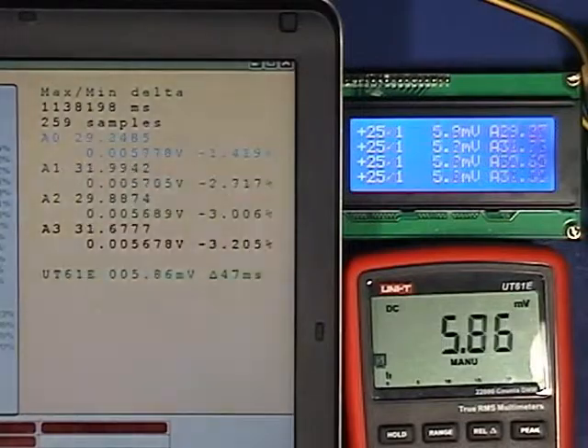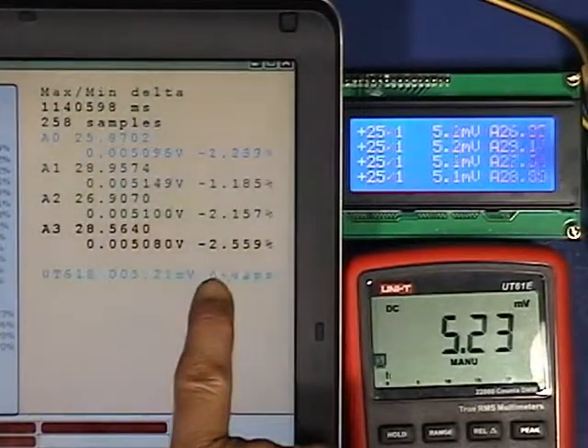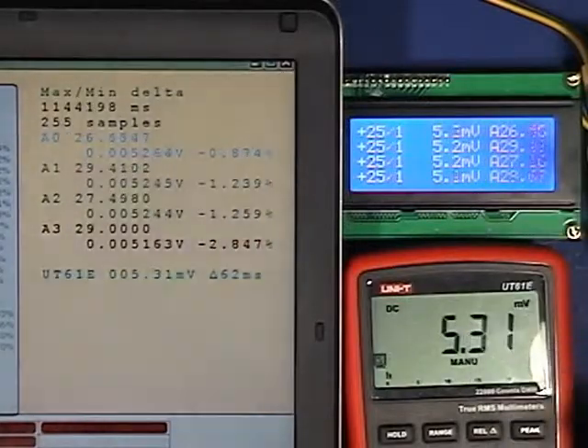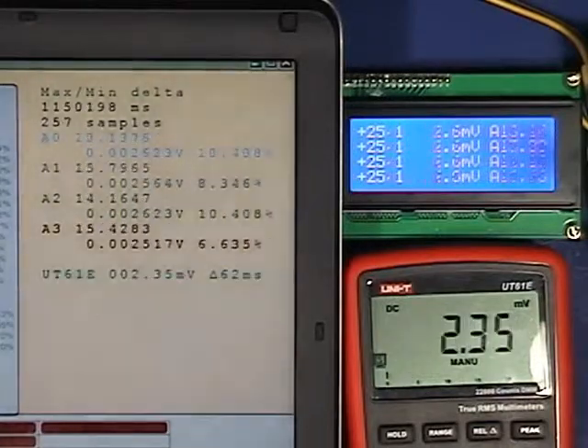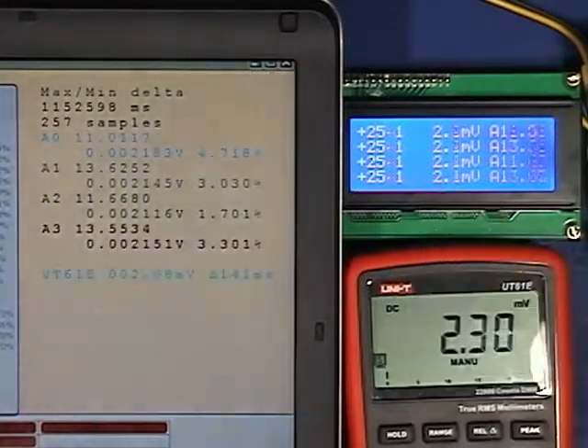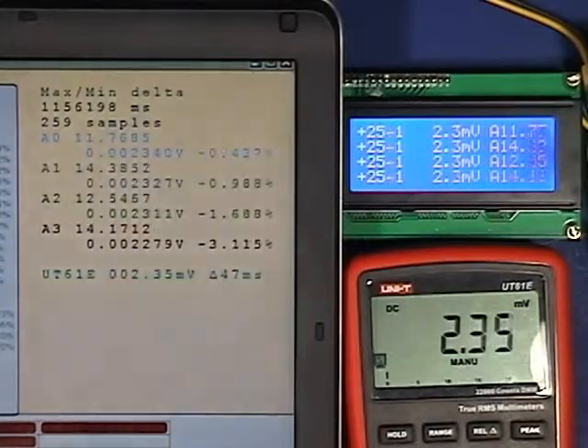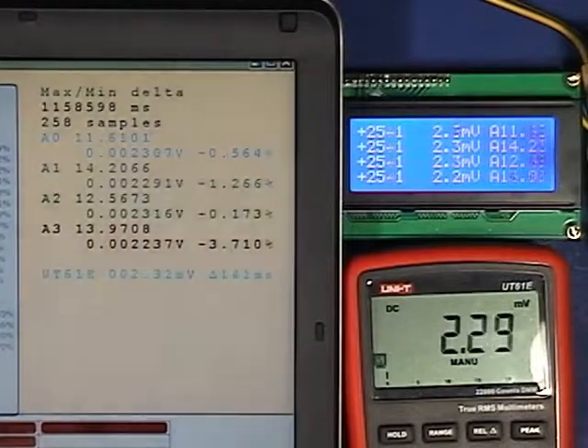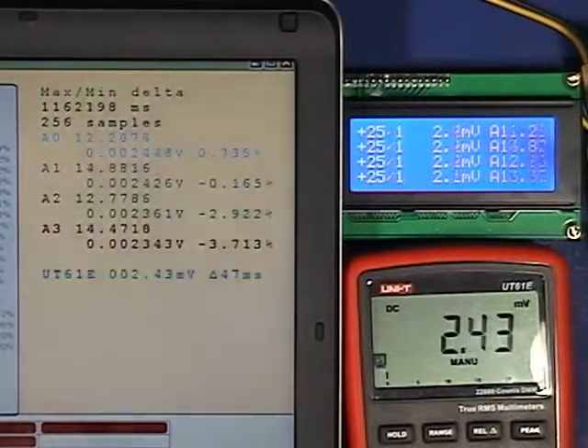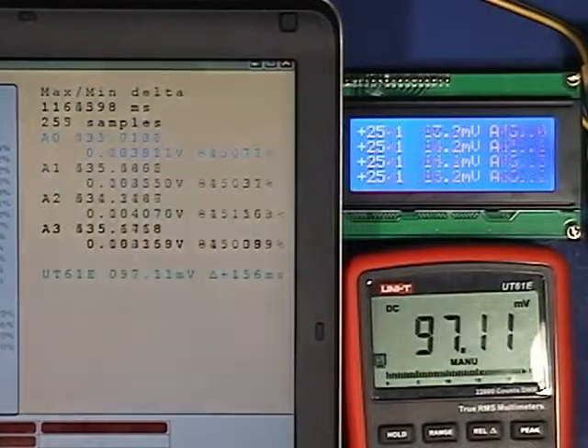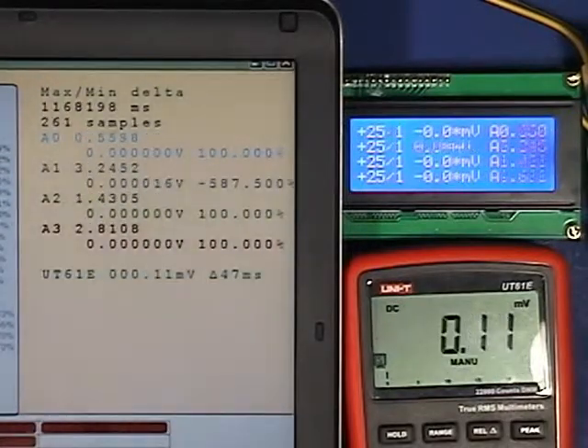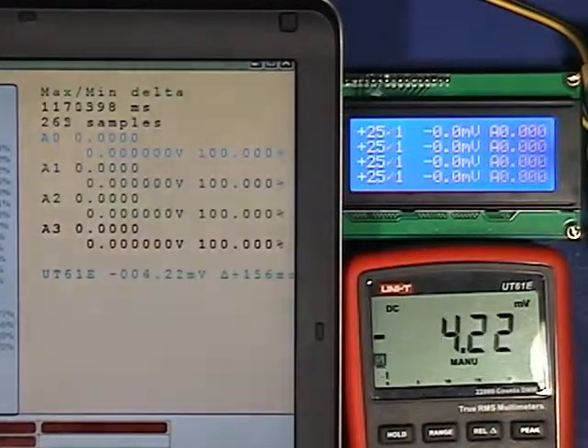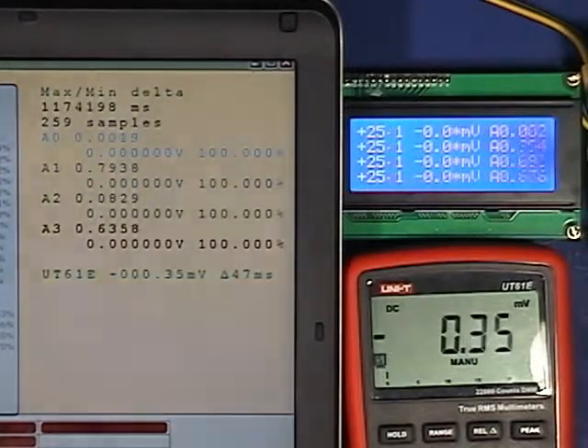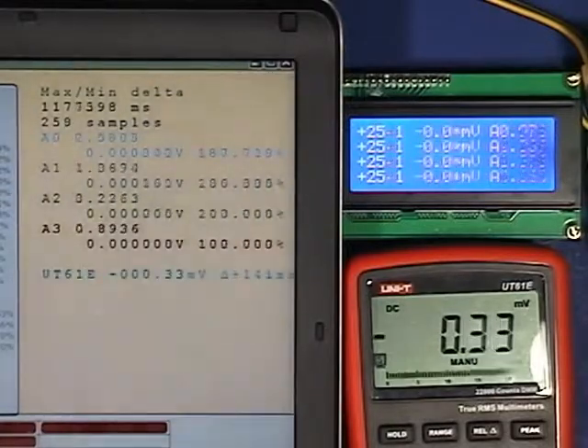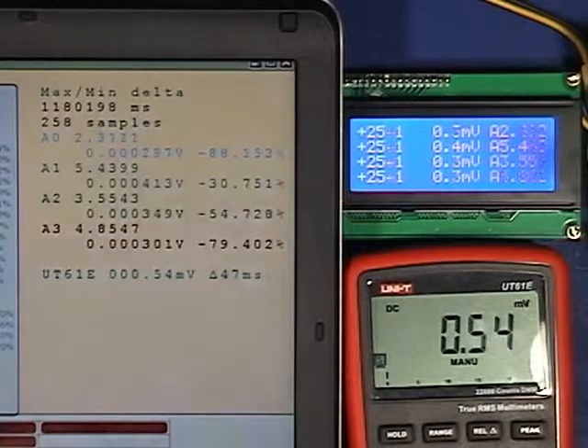6 millivolt. Still reading very respectable numbers, 5.2, 5.25. 2 millivolt. Still reading very respectable numbers. And now we're down to about 5% error. This trim point must not be making good contact. Each time I touch it takes a while to settle in.